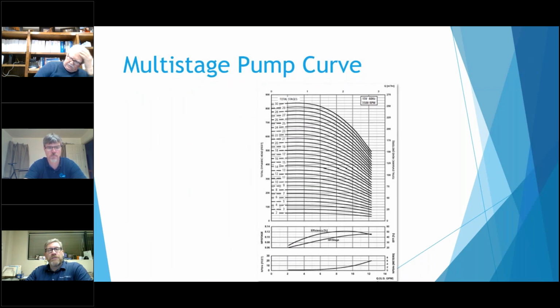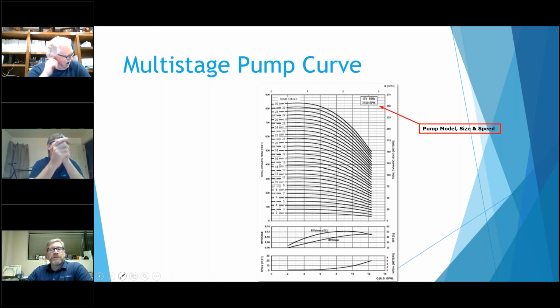This one here is the multi-speed curve or multi-stage curve. So that was the pump that looked like it had a big stainless steel section in between, with the motor on the top and the cast iron housing. These things can be quite tall because it basically just keeps stacking impellers on top of one another. But this is very similar though. So up here in the corner, you got your model number, and this has got your speed up here as well.